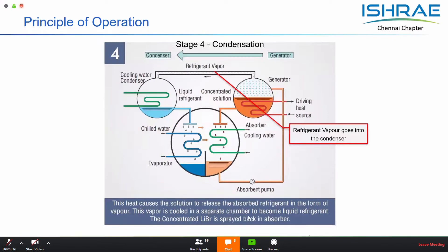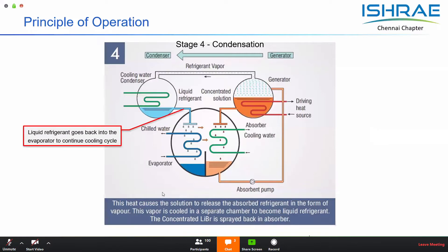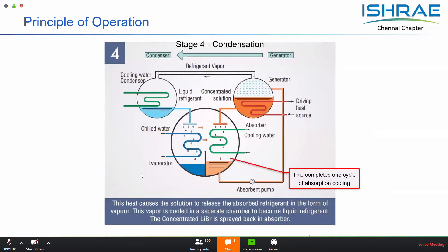The refrigerant vapor is transferred into the condenser, where it exchanges heat with the cooling tower water and gets condensed. This liquid refrigerant is then put back into the evaporator. In a nutshell, this is how the cycle gets completed — evaporation, absorption, regeneration, and condensation are the four stages through which this absorption cycle operates. Once the liquid refrigerant and the concentrated solution are back, this process continues in a cyclic manner.